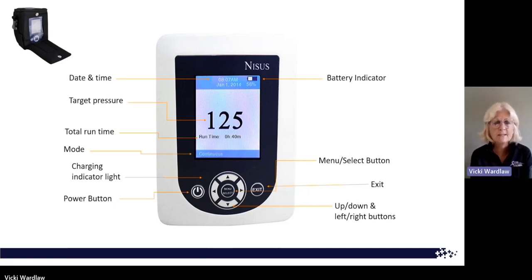Underneath that in the blue, it says continuous. That is the mode. This device is currently set at negative 125 continuous, but there is a variable intermittent option available as well. Variable intermittent means that there's a high pressure and amount of time, a low pressure and amount of time, never dropping off to 0. We know that that really causes problems with the dressings, and you can lose your seal that way. We also know that an intermittent granulates tissue really well. We like to see it used, so ours is a variable intermittent. I'll show you a little bit about those settings here in a moment.